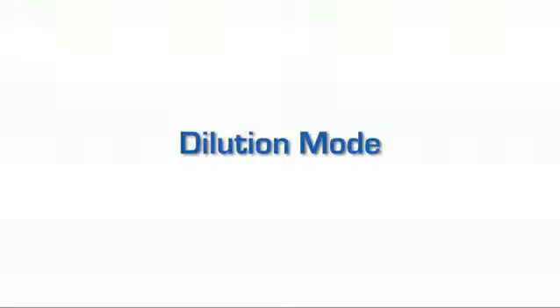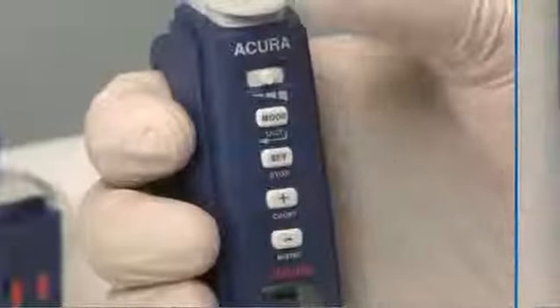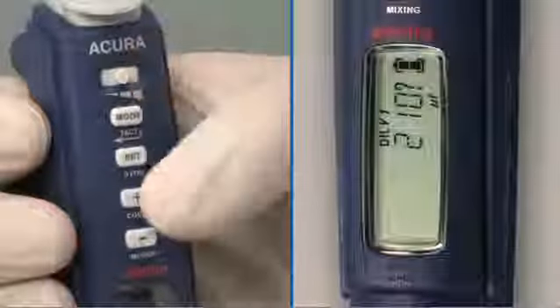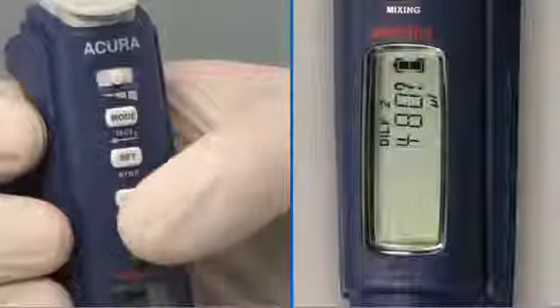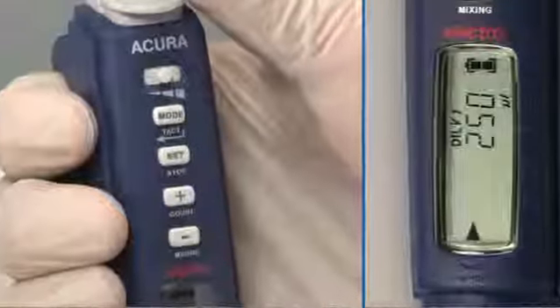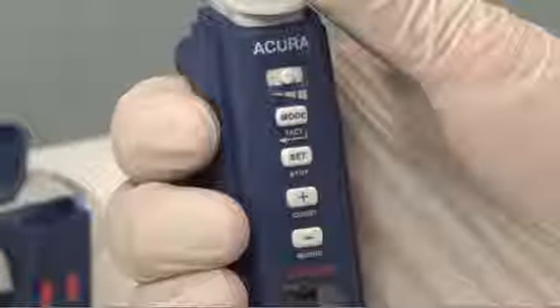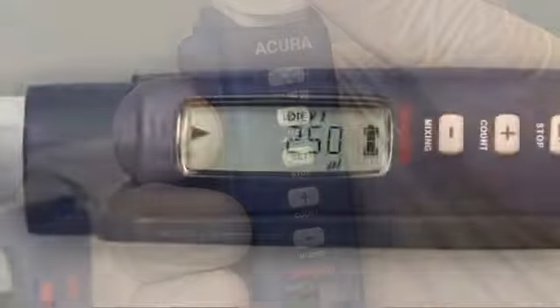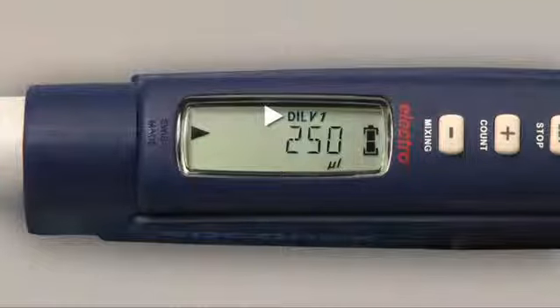Dilution mode is intended for aspiration of 2 or 3 different liquids for restitution in one shot. This is an easy way to dilute samples. Press Mode several times until the display shows Dilute. Press Set to validate. Press the plus/minus keys to display the desired volume for the first liquid. Press Set to validate. Press the plus/minus keys to display the desired volume for the second liquid. Press Set to validate. Should there be a third volume, proceed the same way. Otherwise, just press Set, and the display shows the selected mode and the first volume to be aspirated. The instrument is ready to work in dilution mode.